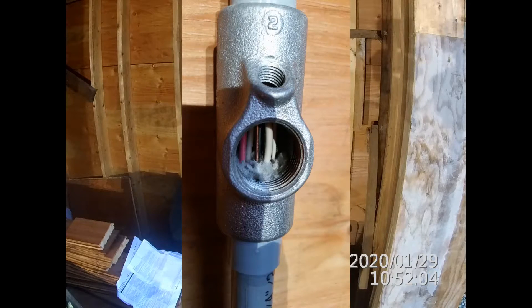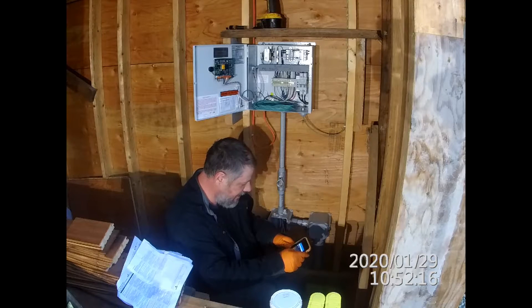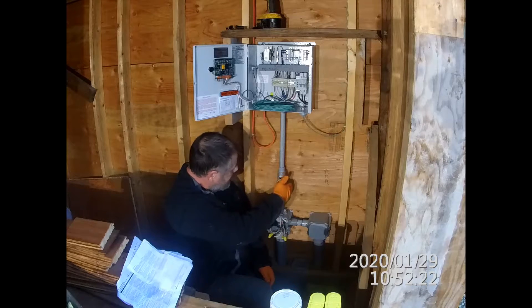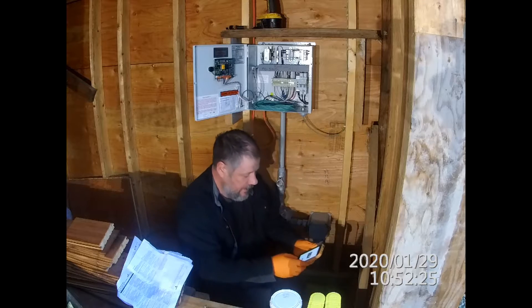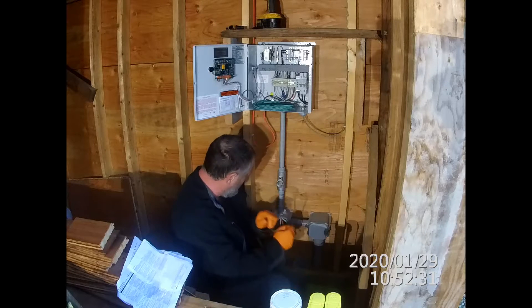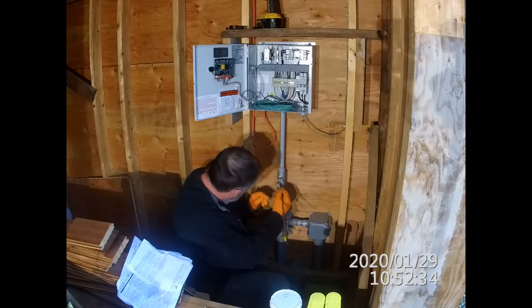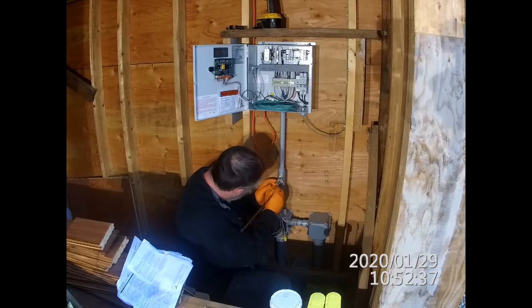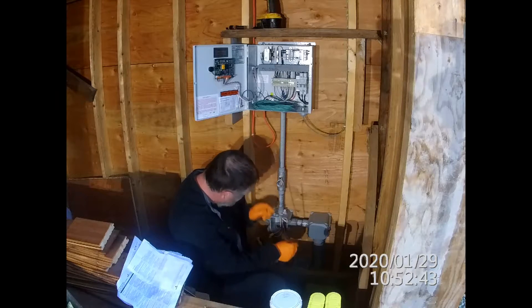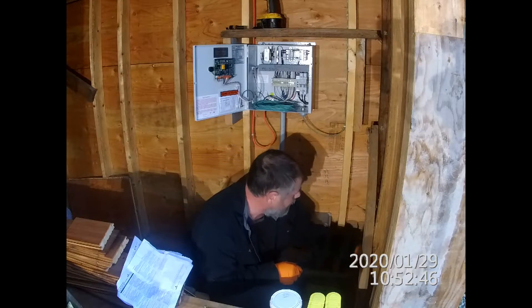You can see here that the conductors all have spaces between them. They say it's important to ensure that the fiber is not adhering to the side of the EYS, so that there isn't a leakage path. The fibers are obviously porous and can allow moisture to seep through. I think we've got it, so now we can put on the main plug.